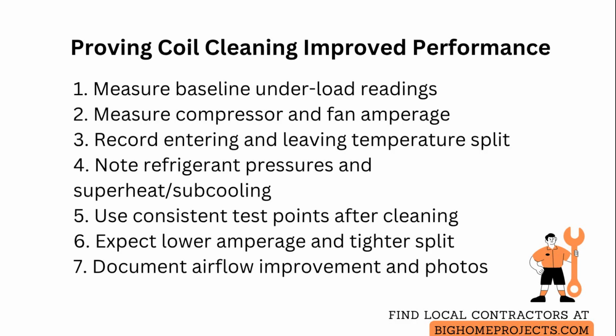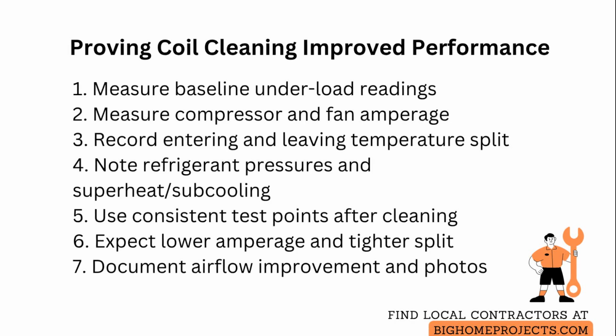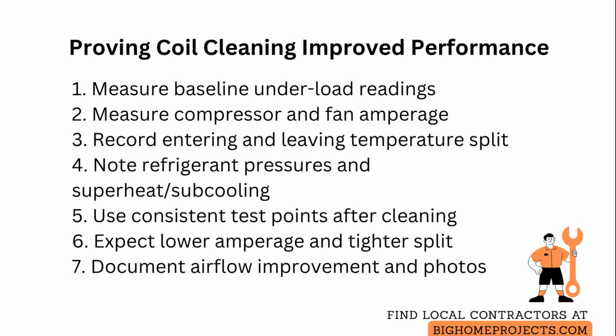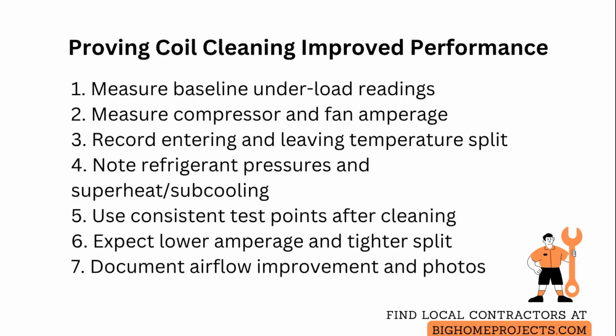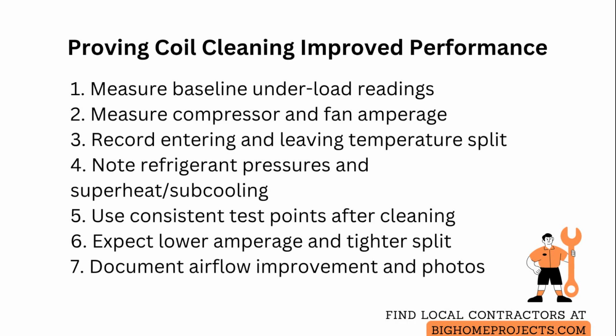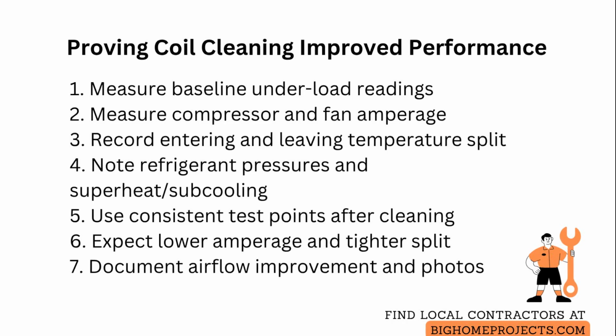Record the temperature split across the evaporator or the condensing unit as appropriate, meaning the difference between the entering and leaving air temperatures, and note the refrigerant pressures and calculated superheat or subcooling using a temperature probe at the service port. Use the same test points and instrument placement after you clean the coil so the comparisons are valid.